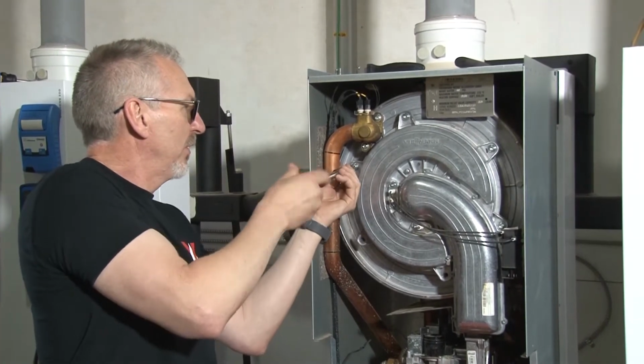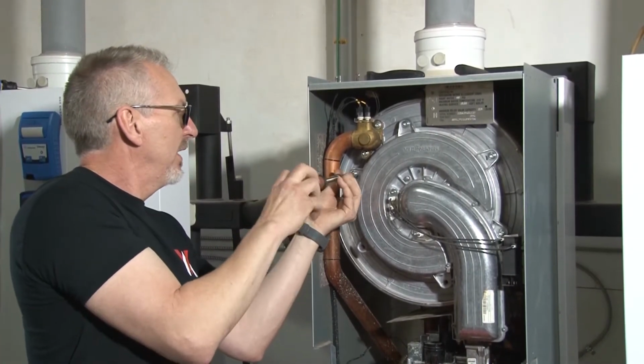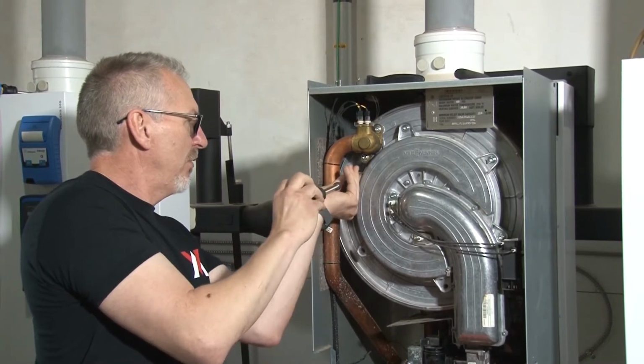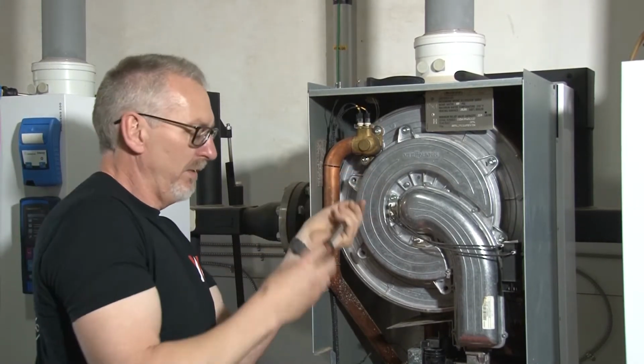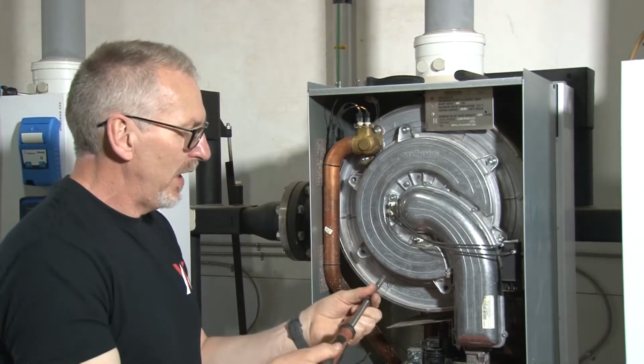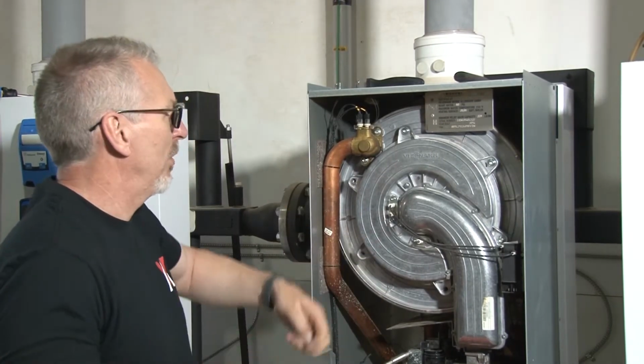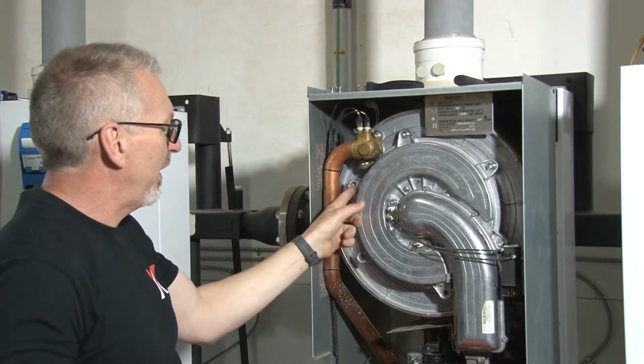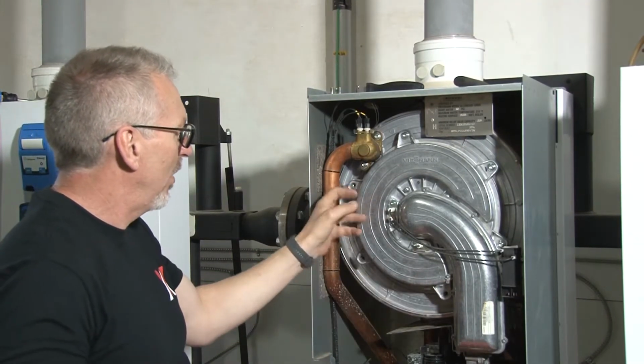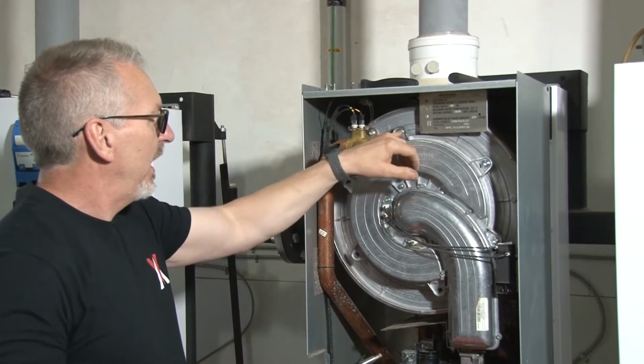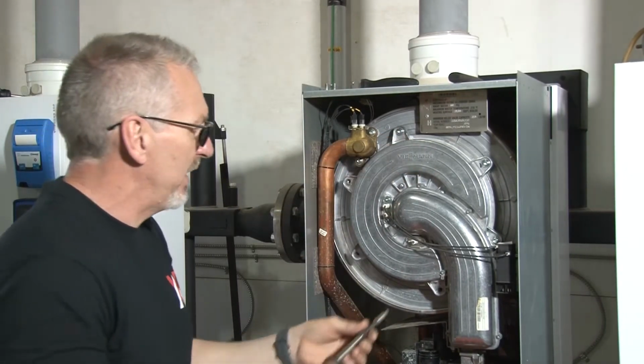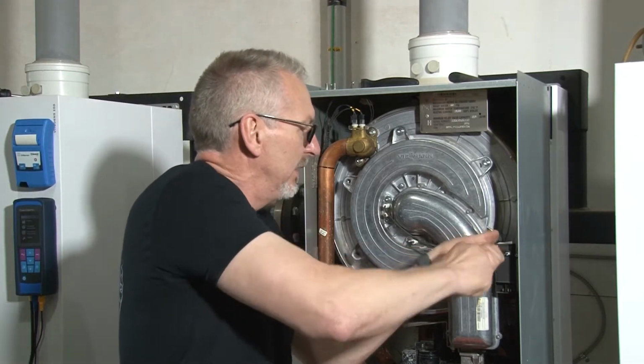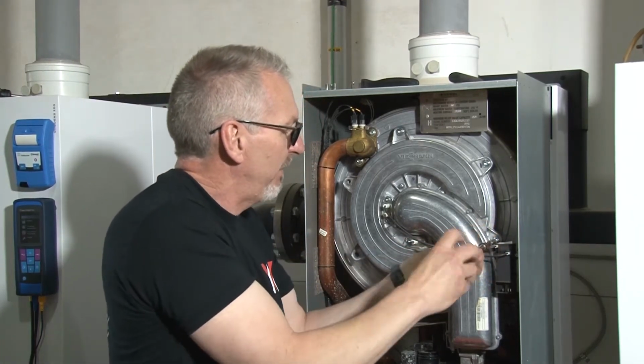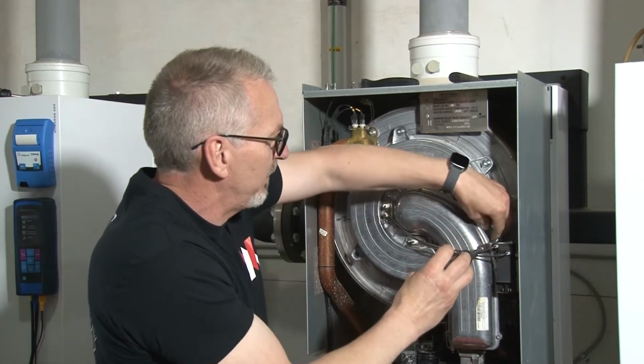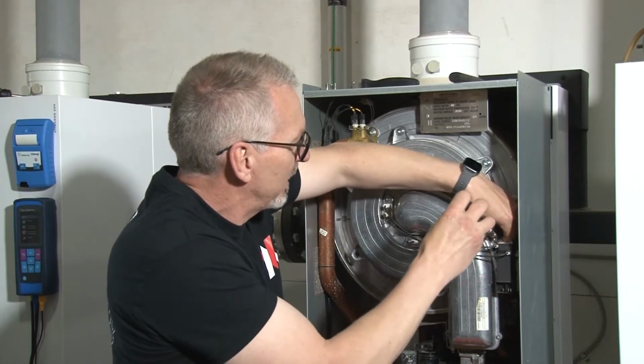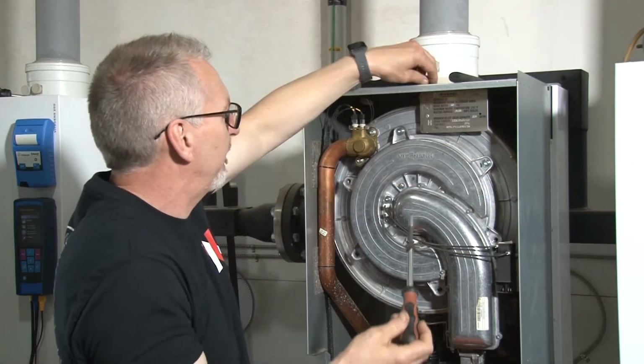But Viessmann sells this little tool here, and it's not a torque wrench. The idea is that you're going to use basically the strength of your forearm, which I like better on a screwdriver than having a ratchet, for instance, where you have a lot more leverage, because you could over torque here without a torque wrench, and you could strip these bolts or the threads inside, and then of course you have to re-tap those. The idea behind this is that you'll have a better feel for the strength of your tightening, so that you don't over torque these bolts when you put them back on. So we'll take these guys out.